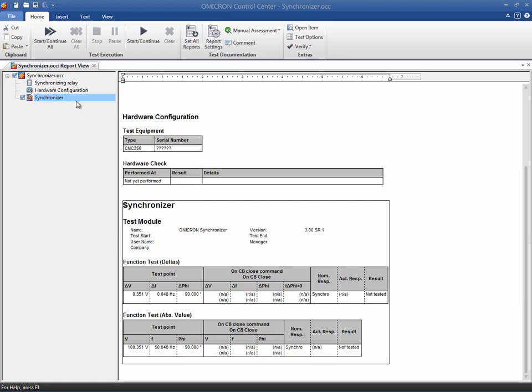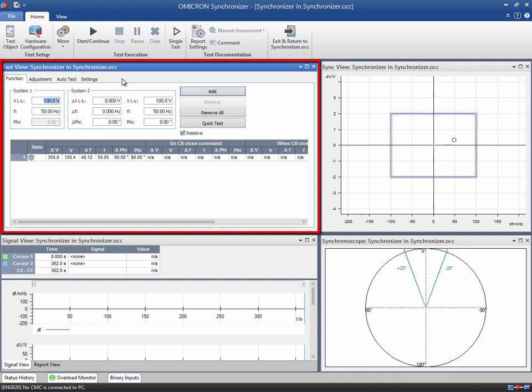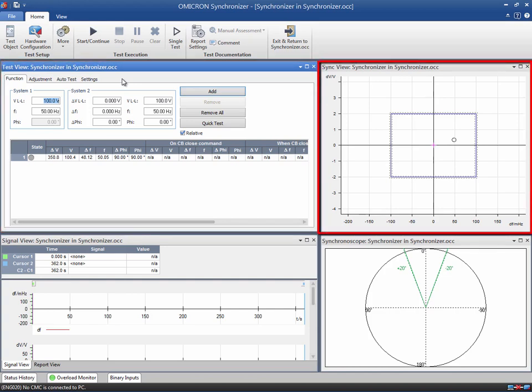The Synchronizer test module is composed of several views. The Test view provides four tabs to parameterize the test. The Sync view contains the relay's synchronization characteristic. It shows the difference in voltages versus the difference in frequency from System 1 and System 2. The test points will be depicted in this diagram.